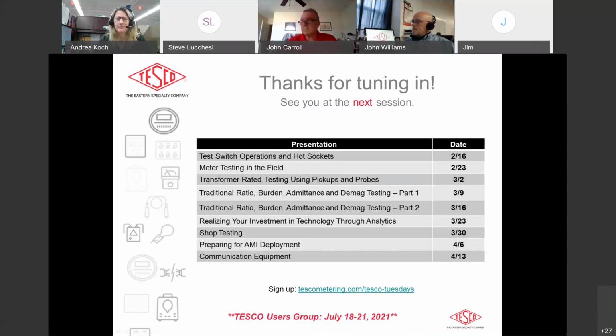Well, I'm still hanging around here, but the 2S meter may not be Blondel compliant per se, but it's still amazingly accurate because it's just a single winding. It's a simple single phase winding. It's not different phases. It's the same phase entering and returning from the service. So whatever's going on the supply side is going on the return side as well. Yep, they're balanced. They're always the same. KVA in must equal KVA out. So there's really not much reason to move away from it.